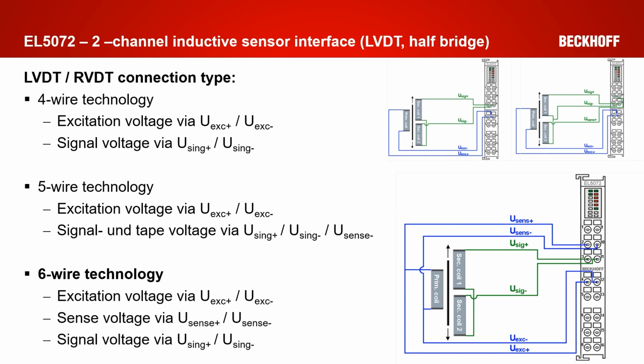6-wire technology also offers the possibility to measure the excitation voltage in parallel with a signal with the sense lines, without current and with high impedance. So the elimination of line-related errors is realized here. We also have ratiometric measurement that is used, and the signal voltage and the excitation voltage are put into relation, and also better accuracy can be realized.